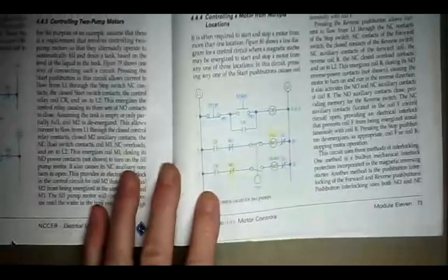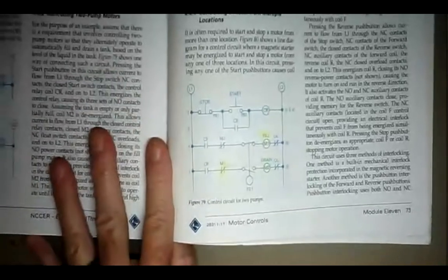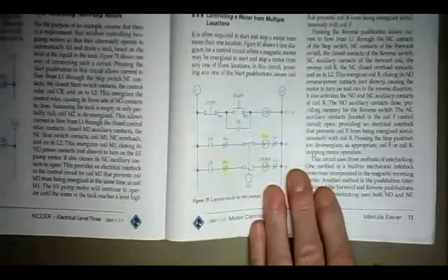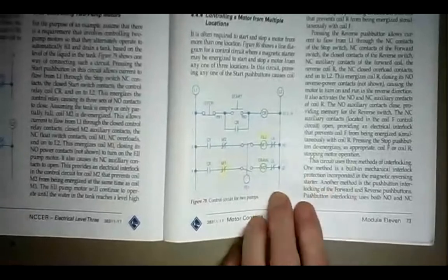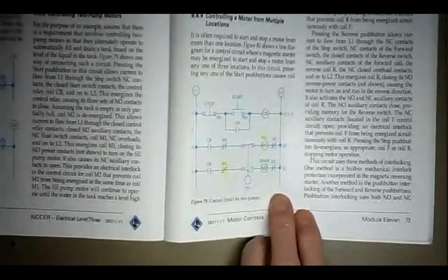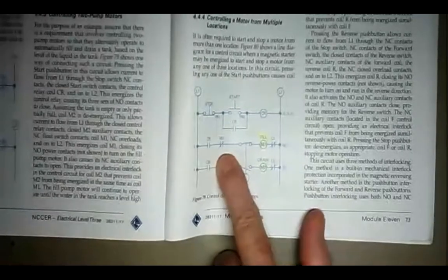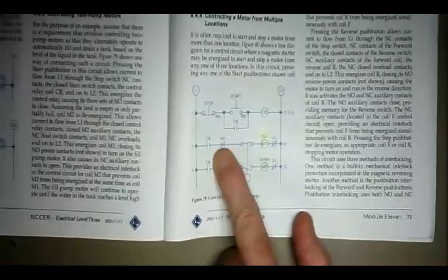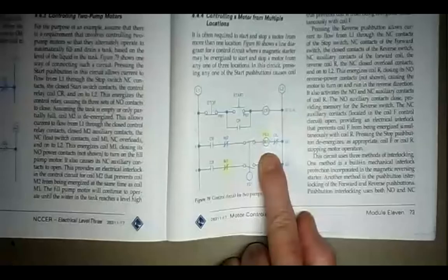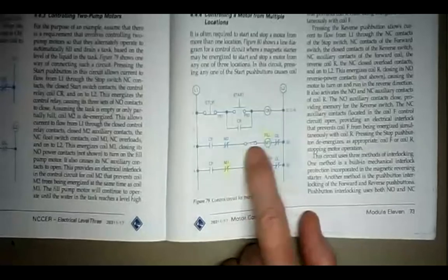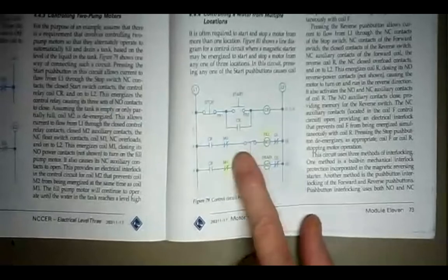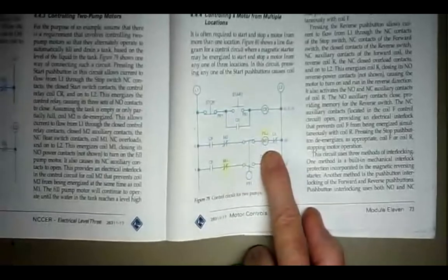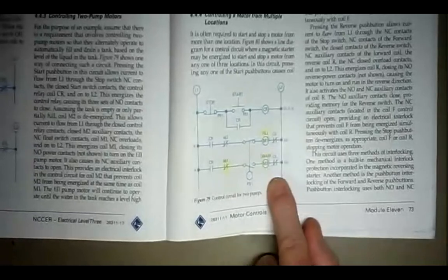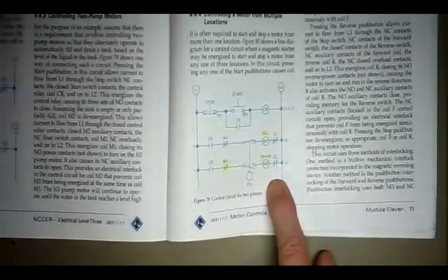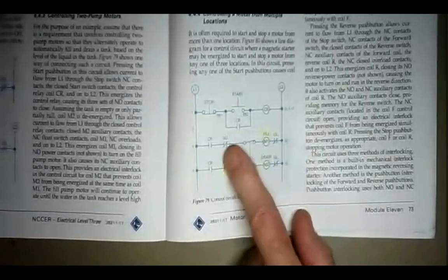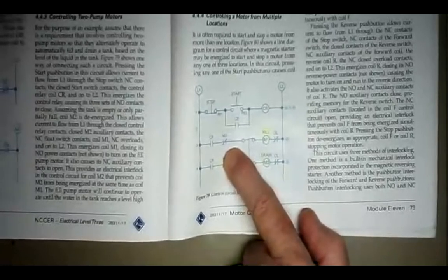Way down at the bottom of page 73, they have an example of electrical interlocks. And I want to explain what we have here. Electrical interlocks make sure that no two things happen at the same time. So here's a normally closed contact from M2, the drain pump, in series with the fill pump, M1. So if you're draining the tank, this normally closed contact is open and there's no way to energize the fill pump. You don't want to be filling and draining at the same time because you're not going to get anywhere. So when the drain pump is on, the fill pump cannot be energized because of that normally closed contact.